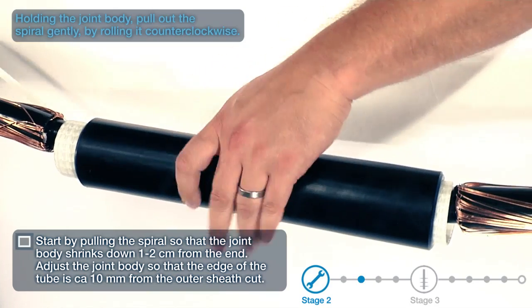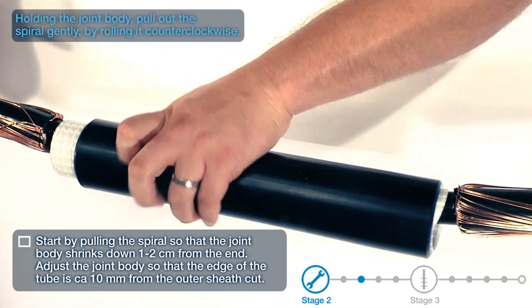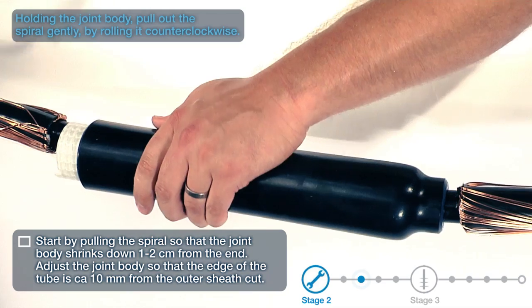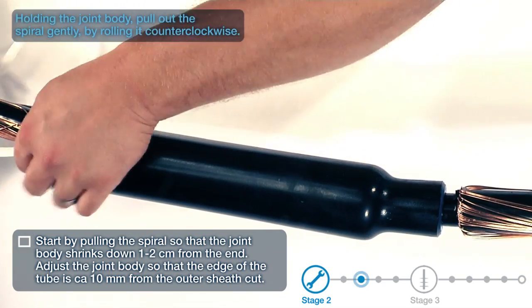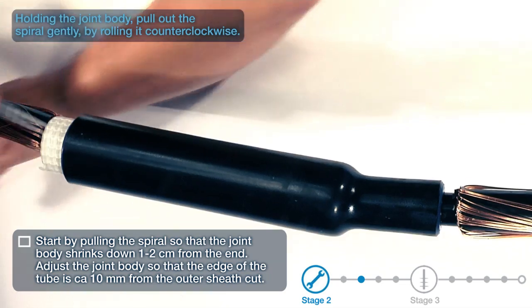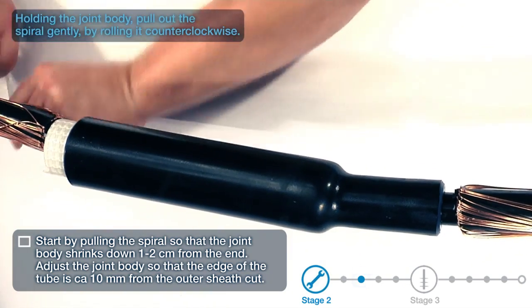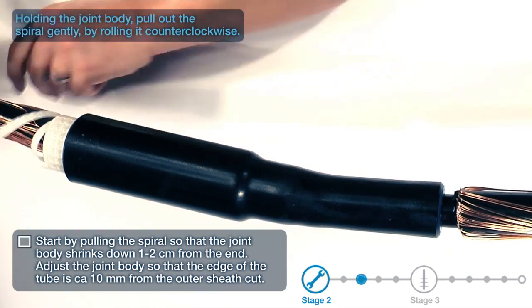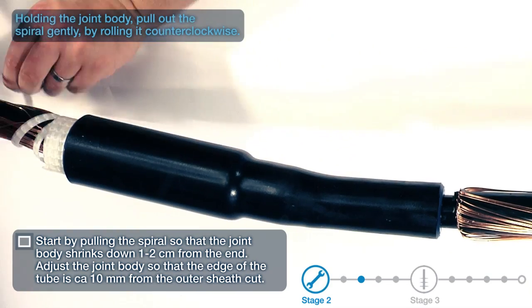Start by pulling the spiral so that the joint body shrinks down 1 to 2 centimeters from the end. Adjust the joint body so that the edge of the tube is CA 10 millimeters from the outer sheath cut. Holding the joint body, pull out the spiral gently by rolling it counterclockwise.